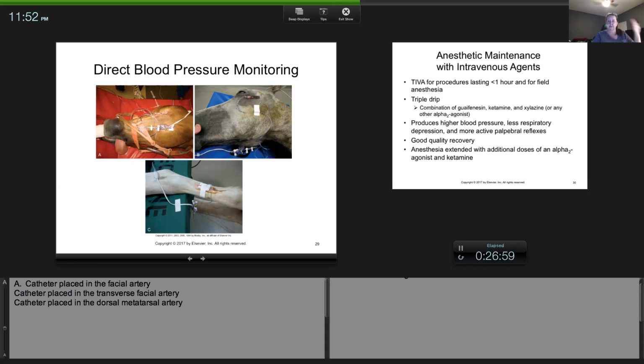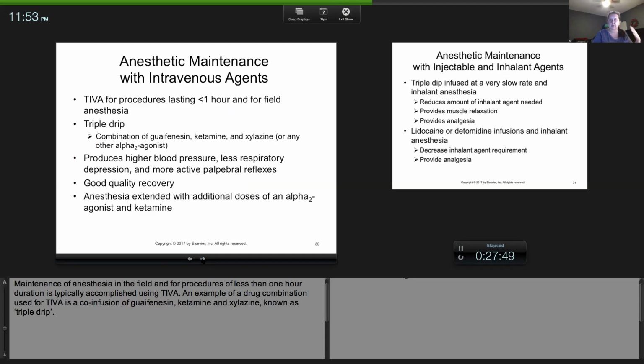If you're going to work with horses, this is the gold standard. You're really going to do direct blood pressure monitoring for two reasons. It's the most accurate. The second reason is, I told you in horses we like to do something called a blood gas. It tests for their pH and their oxygenation status. When we do a blood gas on a horse, we can draw out of this catheter, because remember, to check oxygenation you need an arterial sample. If this is already hooked up in the artery, there's a way to hook up a syringe and take a sample.